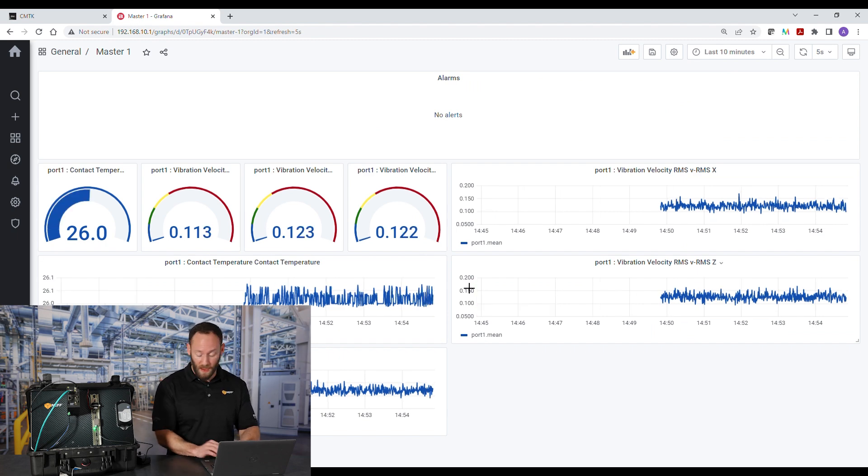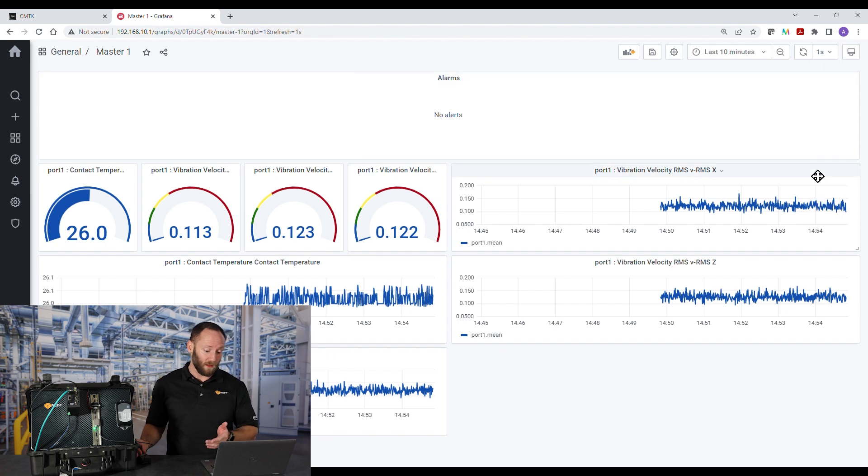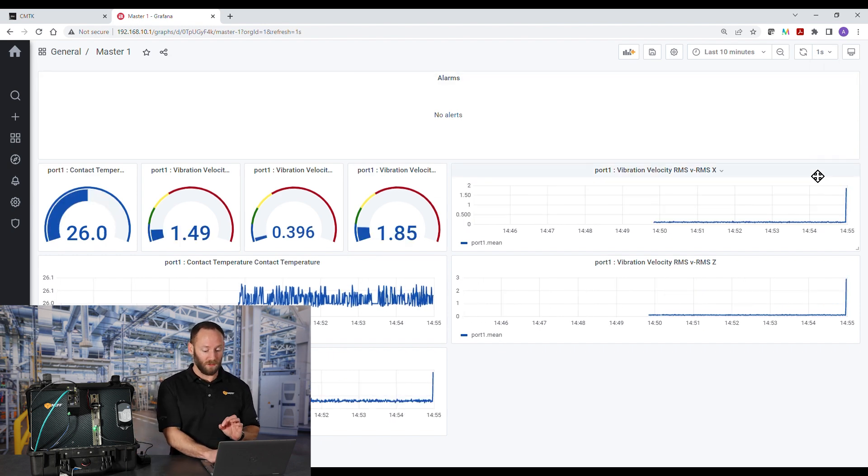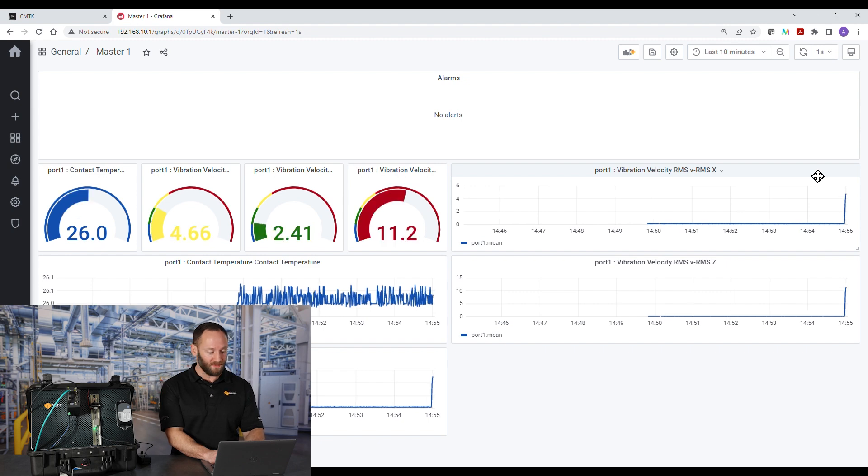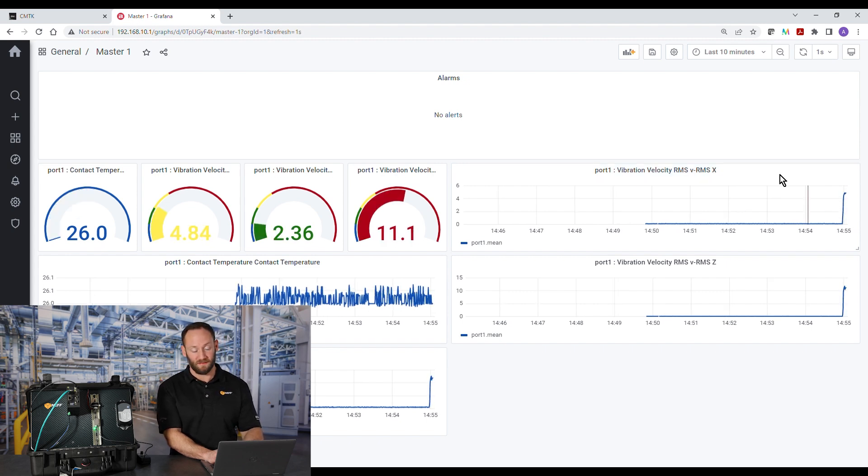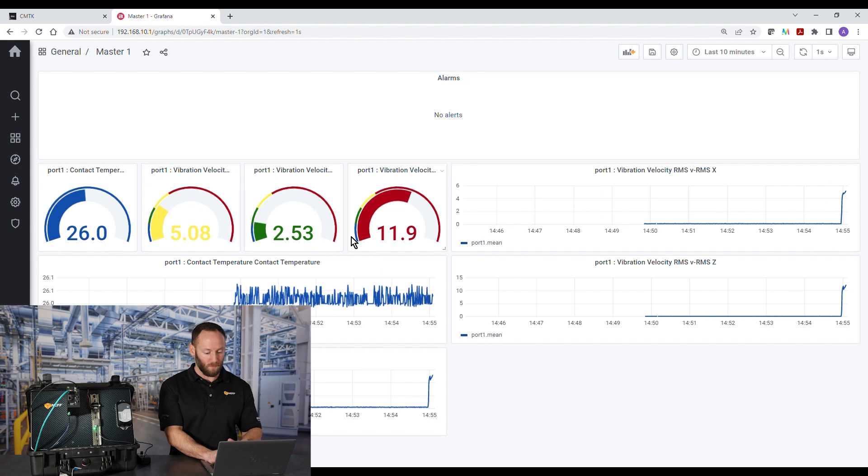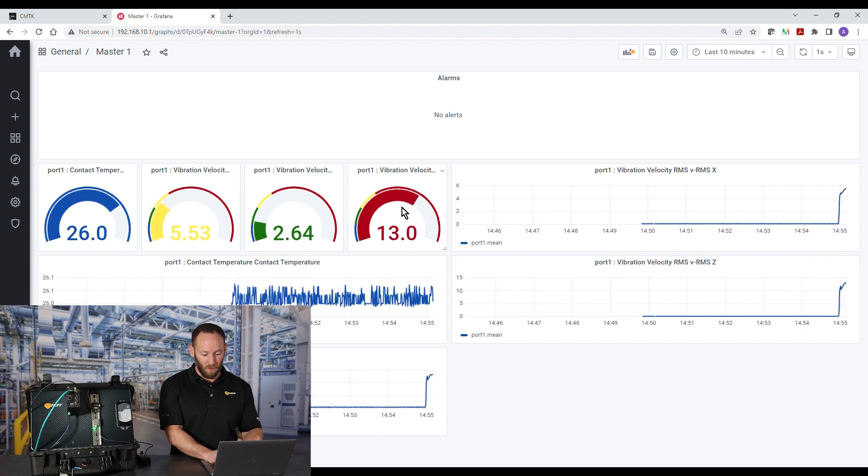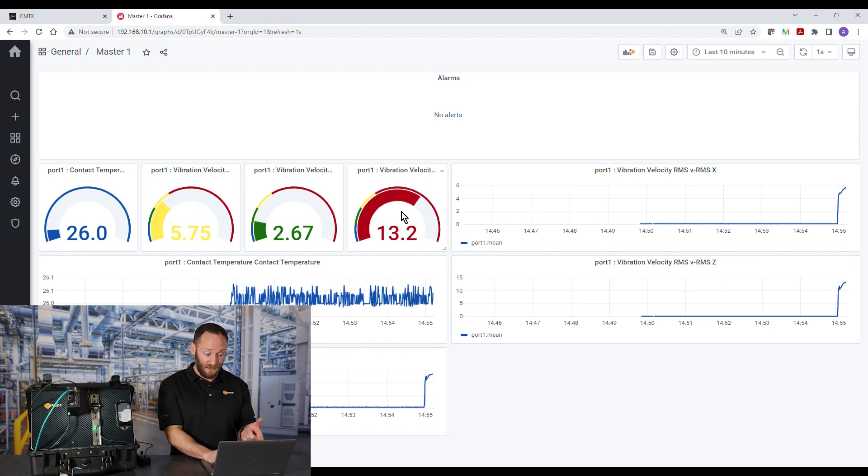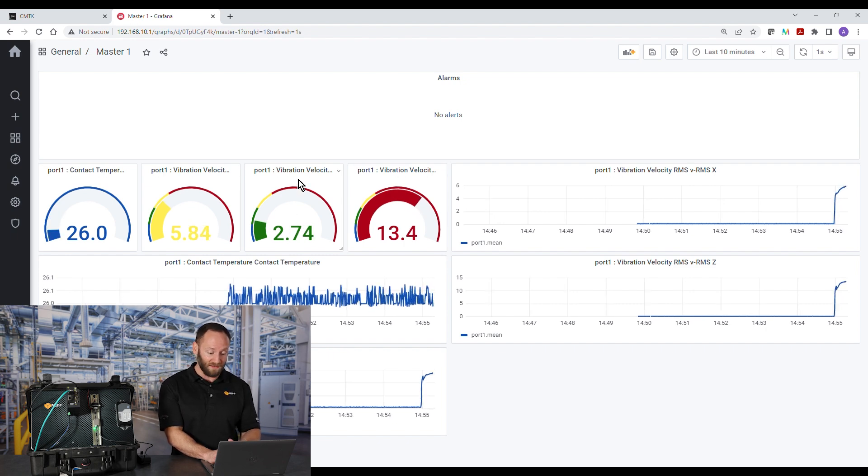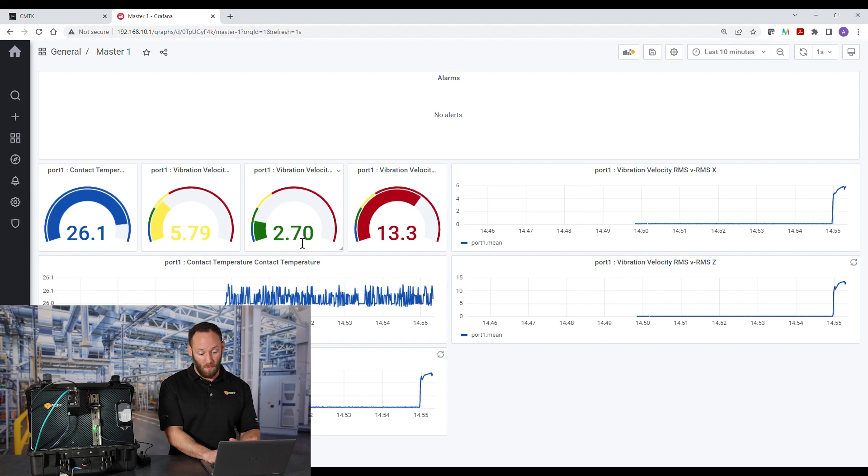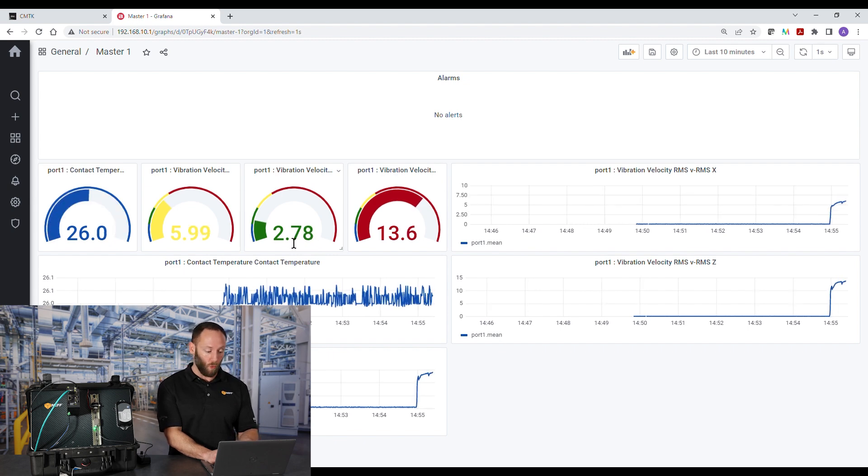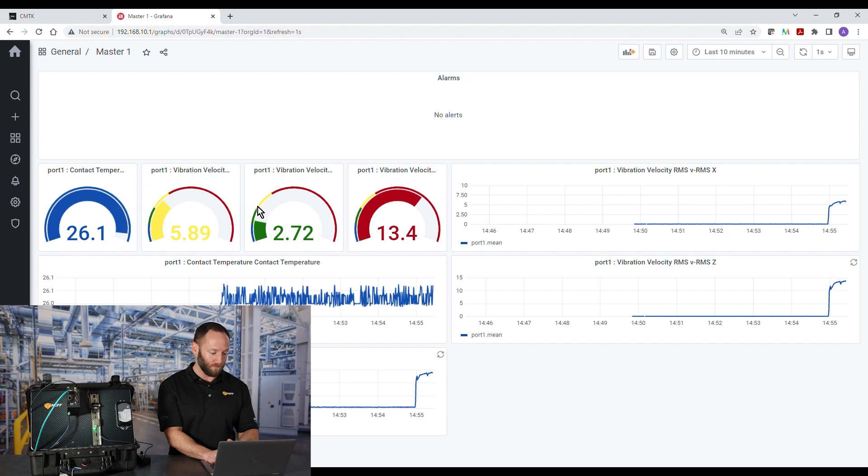So now, when we turn the motor on, our unbalanced motor, we'll see the color change on each axis. And this is really important because it showcases the importance of multi-axis vibration sensing. We can see the unbalanced motor is impacting the X axis, and then it's already in severity zone D, which is the danger zone, whereas vibration velocity on the Y axis is still green in the normal operating mode. Again, this really showcases the importance of multi-axis sensing.